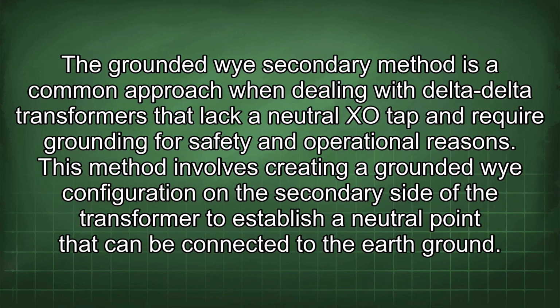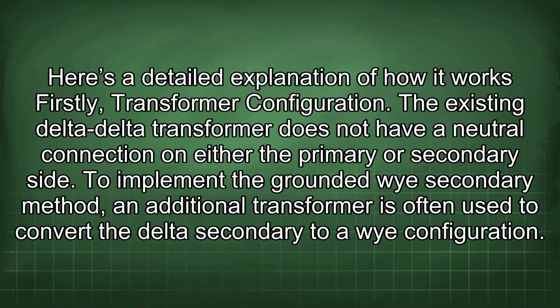The grounded Y secondary method is a common approach when dealing with delta-delta transformers that lack a neutral XO tap and require grounding for safety and operational reasons. This method involves creating a grounded Y configuration on the secondary side of the transformer to establish a neutral point that can be connected to the earth ground. Here is a detailed explanation of how it works.